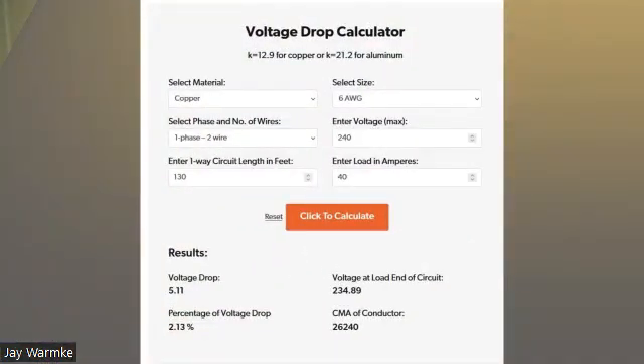And inverters have voltage tolerances. If it's too high, you can actually turn off your inverter. But if you're operating at a higher voltage than it was really designed for, even though it's still working, it's working harder and it may not last as long. So let's give an example here with Blue Rock Station. I have microinverters on my solar array there, and 6-gauge wire running from the microinverters, a 40 amp circuit here, about 130 feet from the array to where it connects in to the grid. So if you look down below, it says I'm going to be experiencing somewhere around a 5-volt voltage drop.